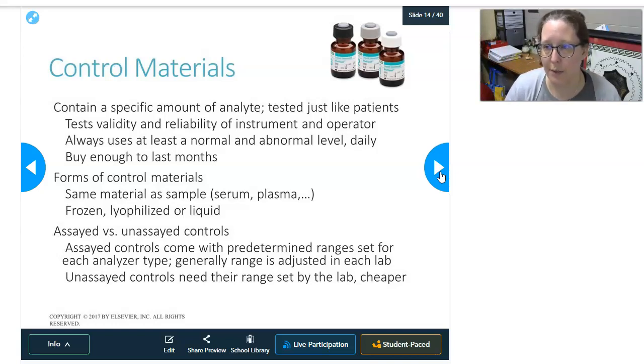And they're tested just like patients are, so in a way you treat them just like you would a normal patient. They usually come in 3 different levels, so that could be a low, normal, and high, or the low could be your normal, and then a little bit high and really high. It just depends, but it should definitely test the range of your analytical measurement range, so that you know your analyzer is operating ideally, precisely and accurately at all ranges of testing up and down the analytical measurement range for each assay that you're doing. Always use at least a normal and abnormal level. That's the bare minimum daily.